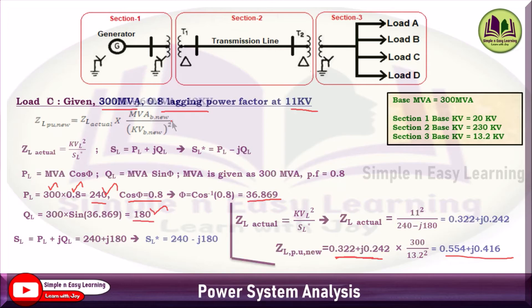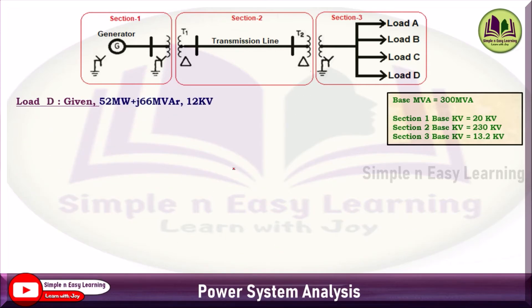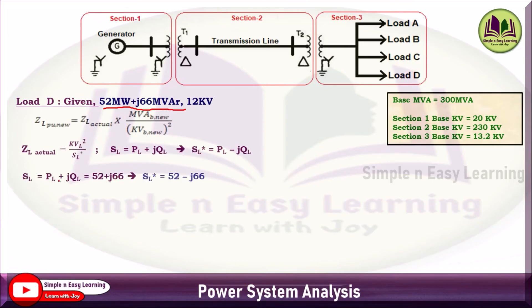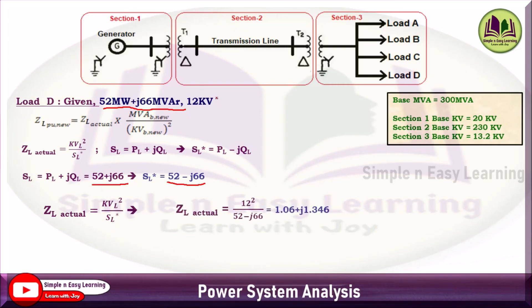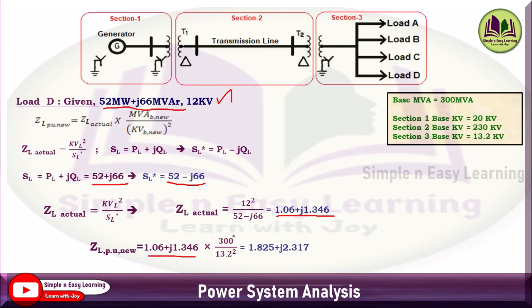Load D: given directly as 52 MW + j66 MVAR at 12 kV. So P_L = 52, Q_L = 66; S_L = 52 + j66; S_L_conjugate = 52 − j66. Z_L_actual = 12² / (52 − j66). Z_L_pu = Z_L_actual × 300 / (13.2²) at Section 3 base kV.